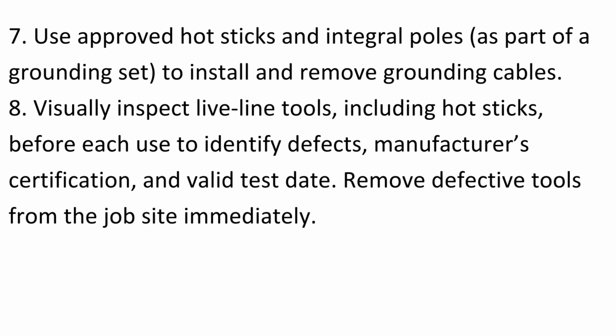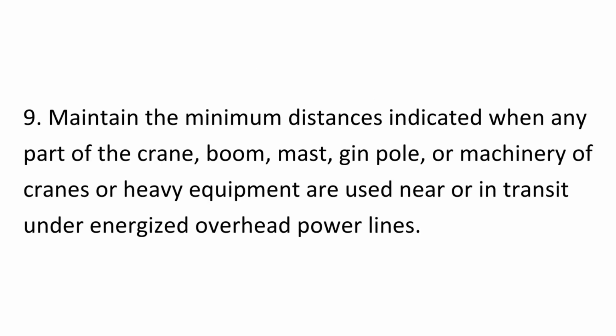7. Use approved hot sticks and integral poles, as part of a grounding set, to install and remove grounding cables. 8. Visually inspect live line tools, including hot sticks, before each use to identify defects, manufacturer's certification, and valid test date. Remove defective tools from the job site immediately. 9. Maintain the minimum distances indicated when any part of the crane, boom, mast, gin pole, or machinery of cranes or heavy equipment are used near or in transit under energized overhead power lines.